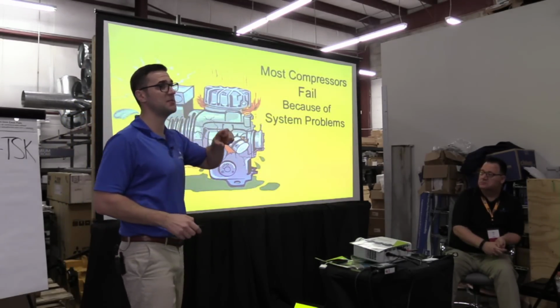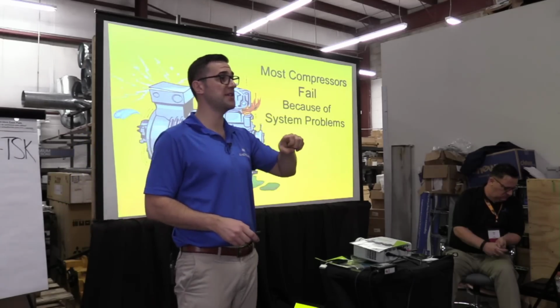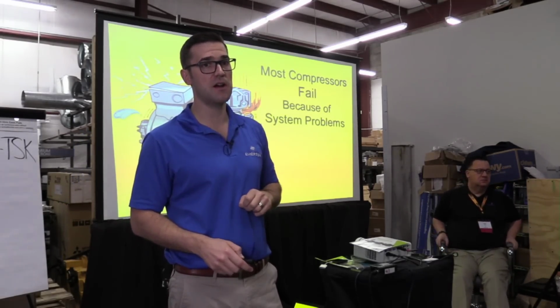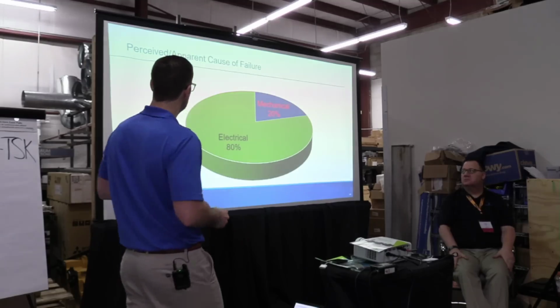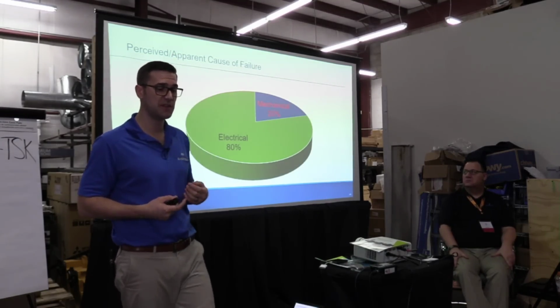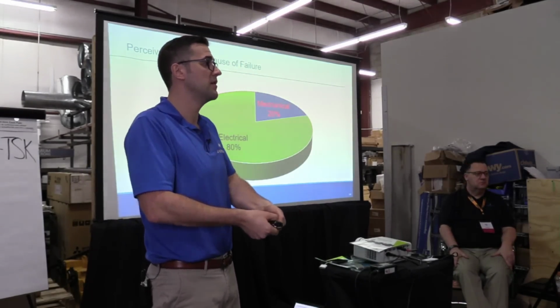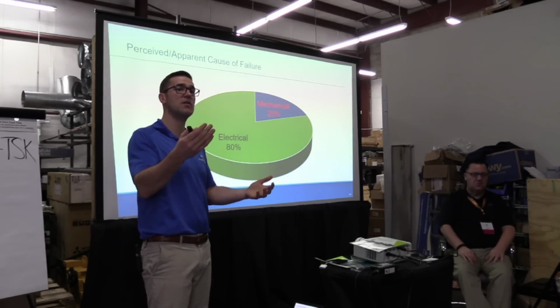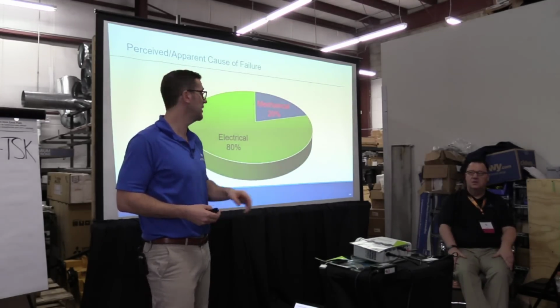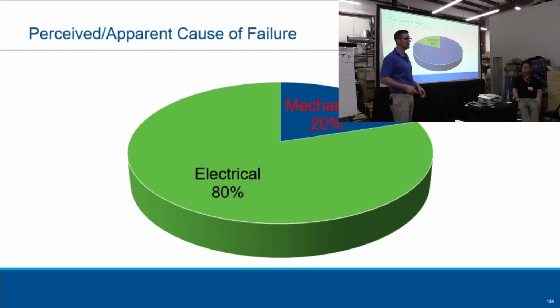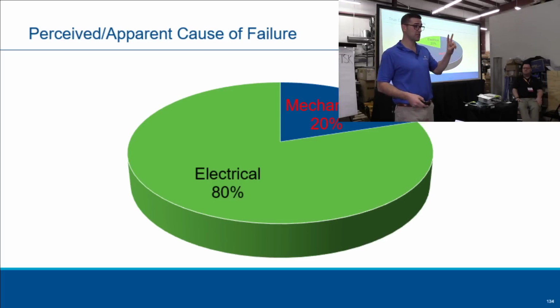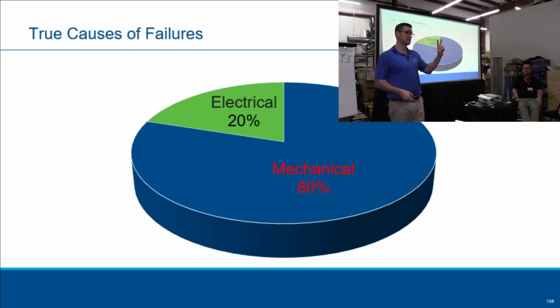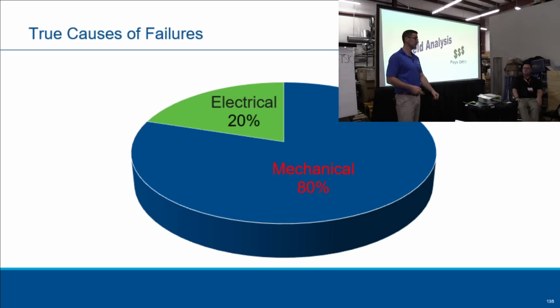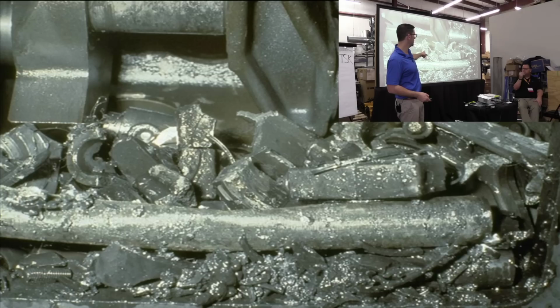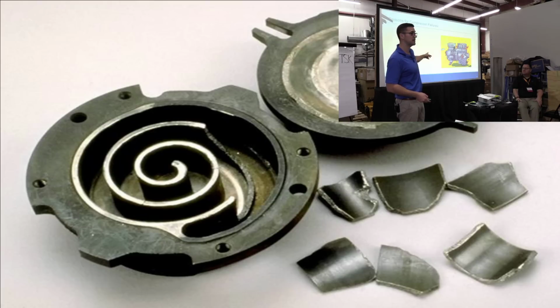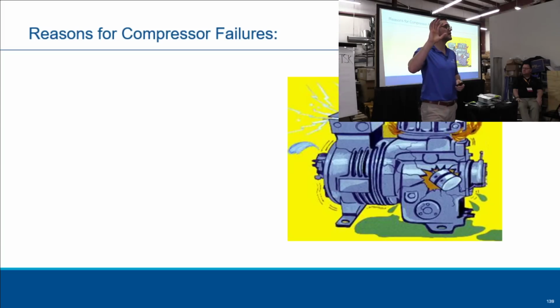Causes and prevention. Most compressors fail because of system-related problems. A lot of people blame the compressor, but it's system-related issues that cause failed compressors. So this is what happens. A contractor, even myself when I was in the field, goes up to the compressor, takes off the wires, ohms it out. Oh, electrical short, it's a burnout. Electrical failure. That's what we get: 80% electrical, 20% mechanical. The real cause is a mechanical failure. Electrical is the second cause of failure. Mechanical is usually the first cause. Field analysis pays off, or your compressors look like this, or like this. So, what are the 5 or 6 things that cause a compressor to fail?